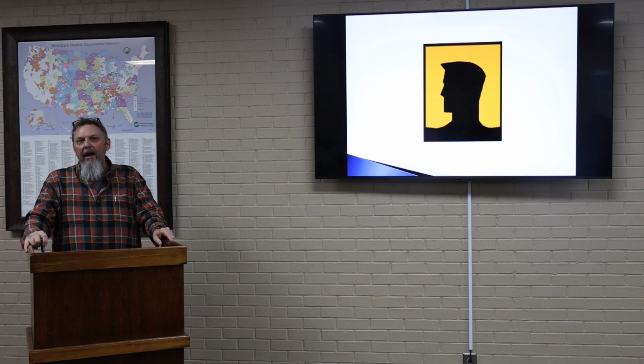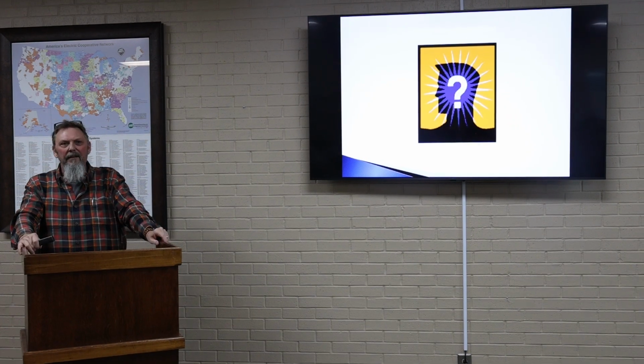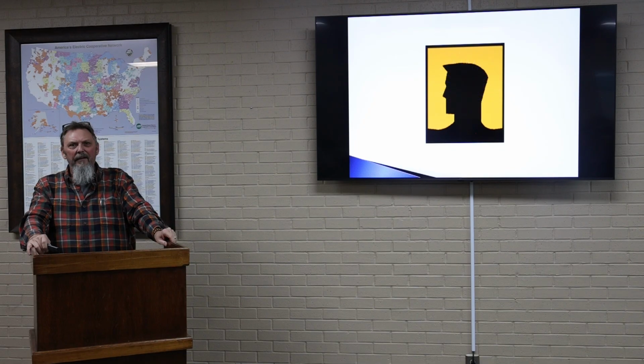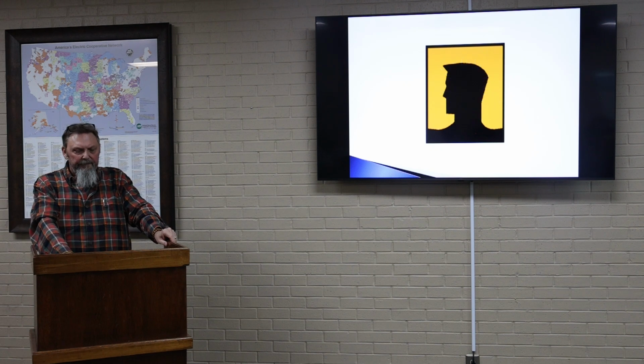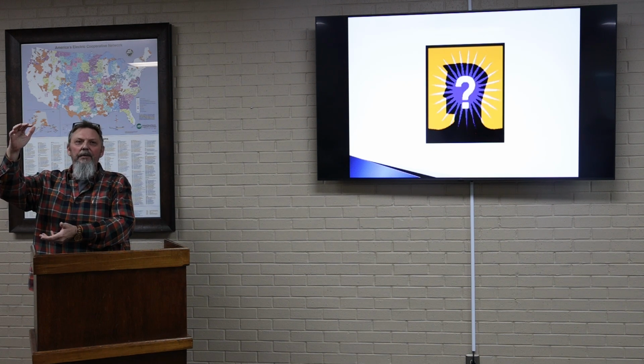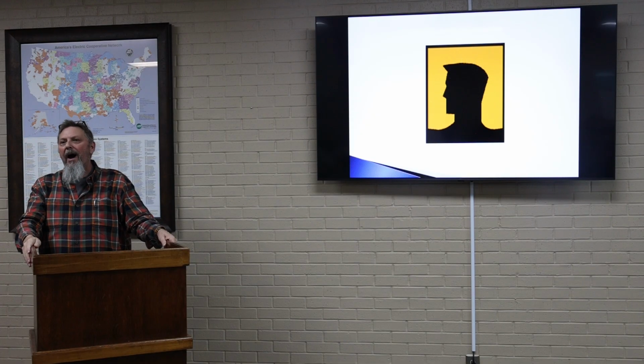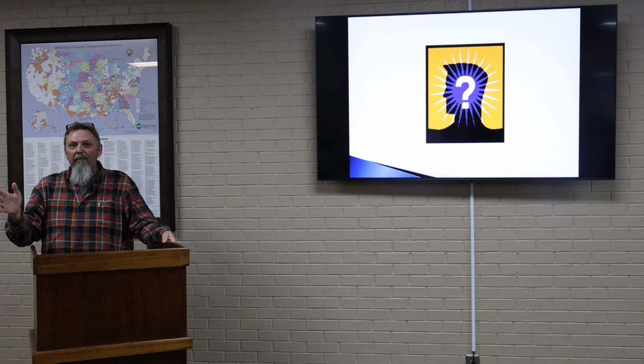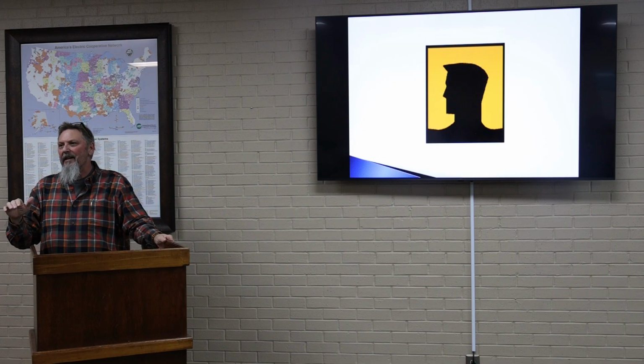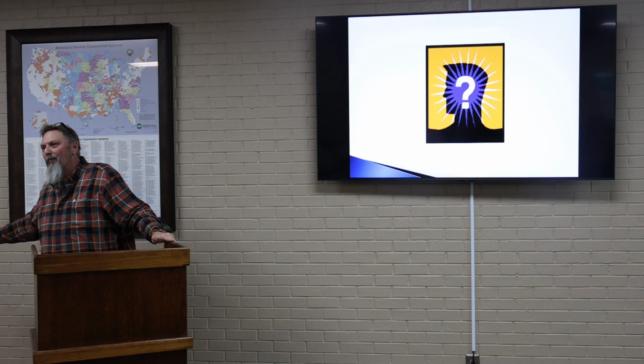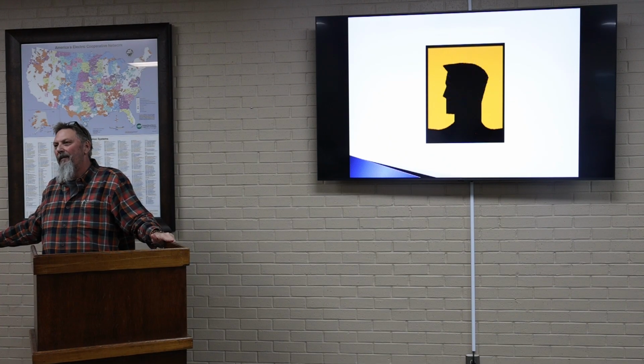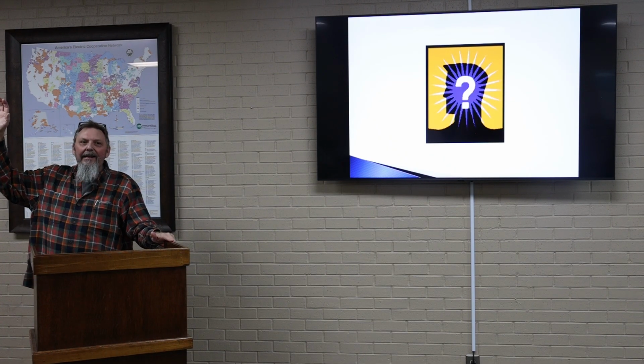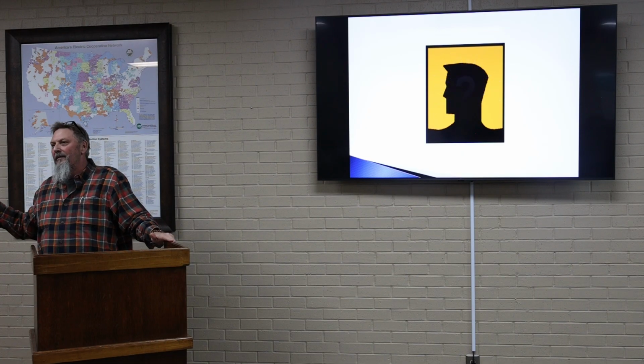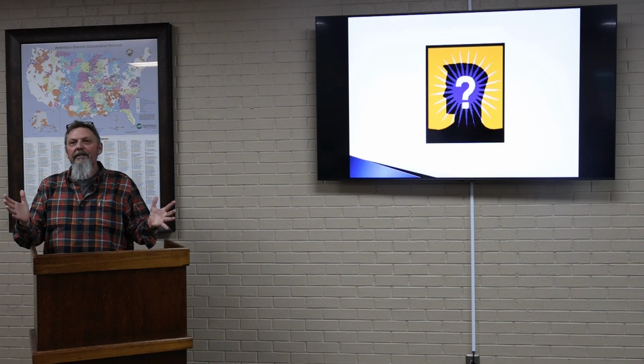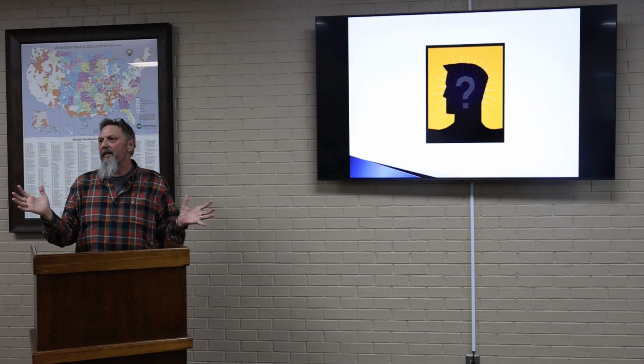We have it set at a minimum now of 119, and it goes up to 126. At the end of the line, they check what the voltage is and use that information to go back to the substation and adjust, to keep everybody within range. So the standards give you that range, up to 126 as a maximum, but that doesn't mean you need to operate everything at 126 volts. Your equipment works perfectly fine at 118 volts, and in fact the voltage at that outlet works fine even at 110 volts. So there's no reason to ramp it up high and use more demand when we can lower it and use less demand. Everything still works perfectly fine within the same ranges, just like before. You won't know any difference.